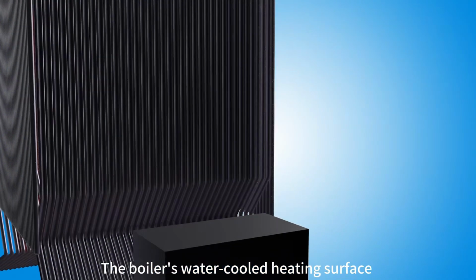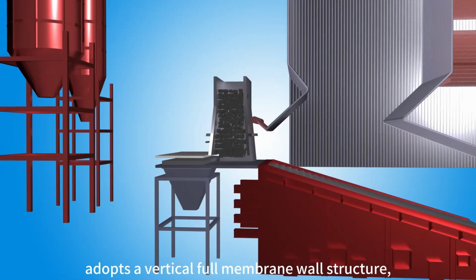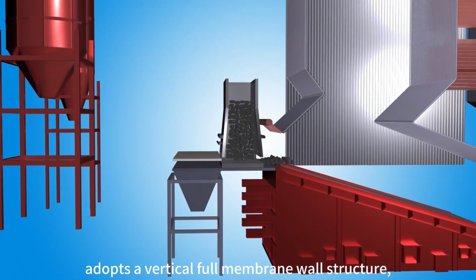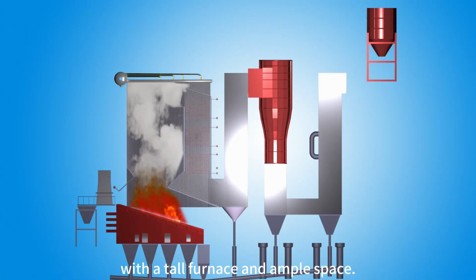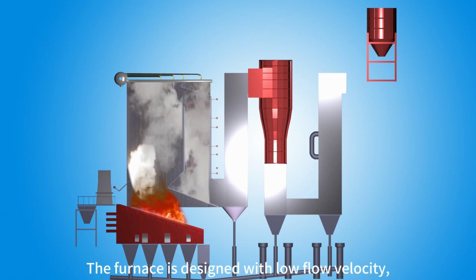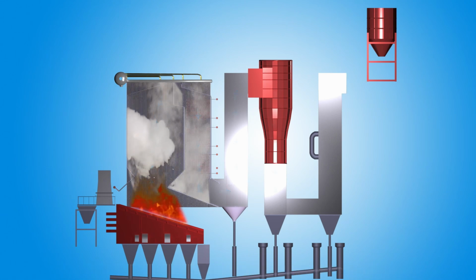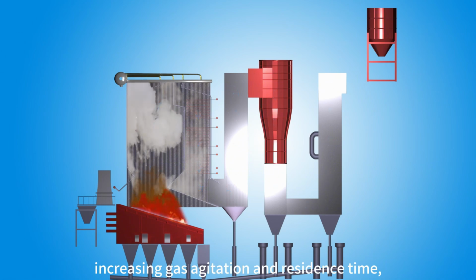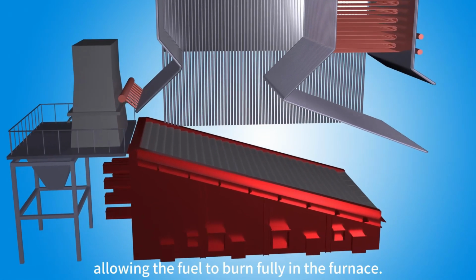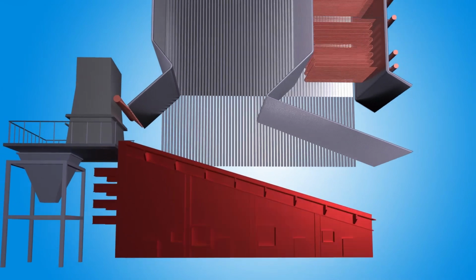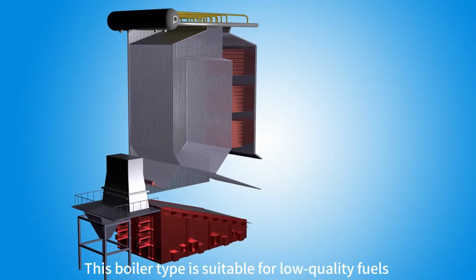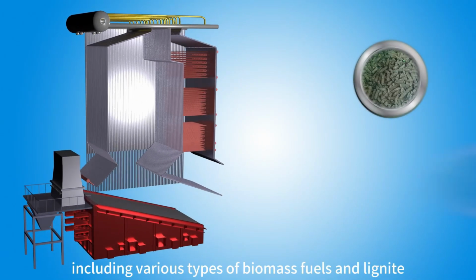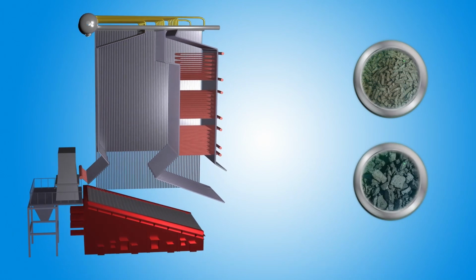The boiler's water-cooled heating surface adopts a vertical full-membrane wall structure, with a tall furnace and ample space. The furnace is designed with low flow velocity, increasing gas agitation and residence time, allowing the fuel to burn fully in the furnace. This boiler type is suitable for low-quality fuels including various types of biomass fuels and lignite.